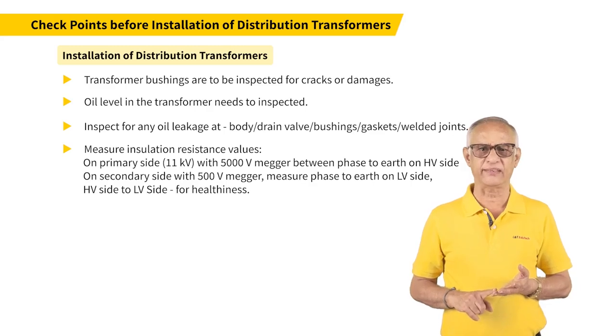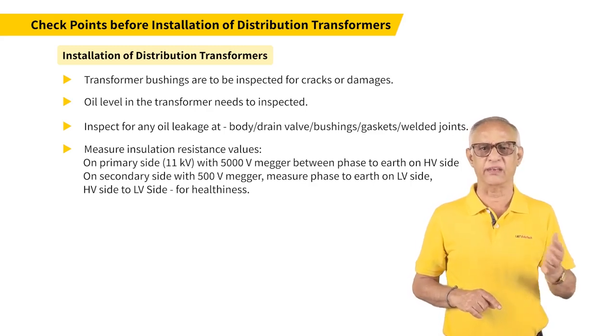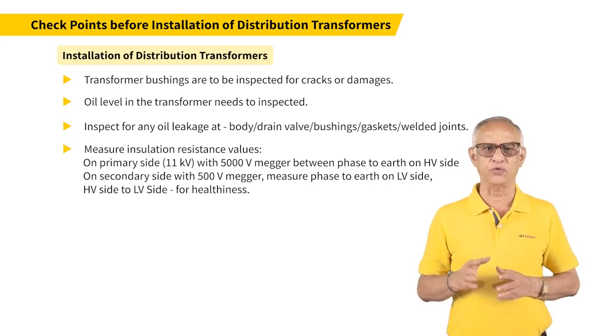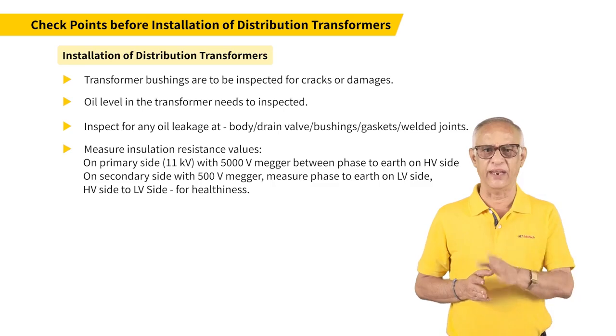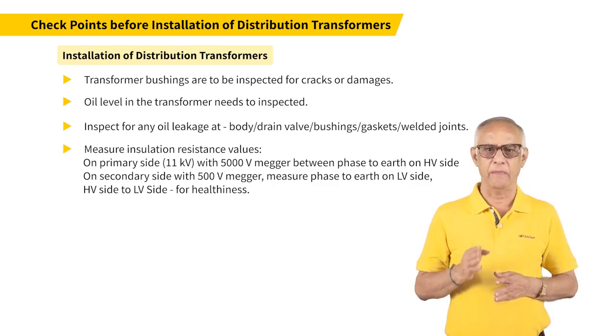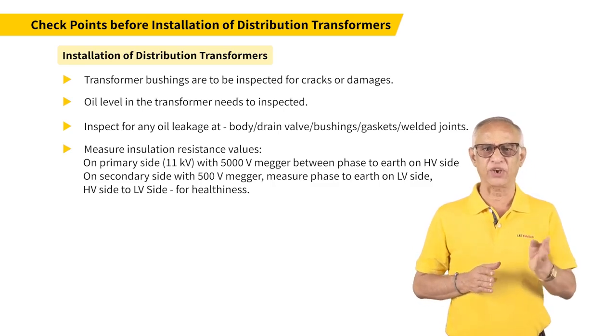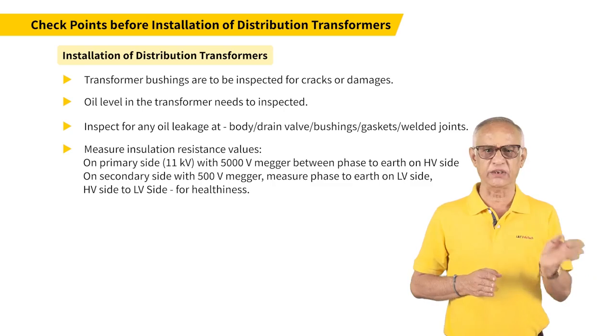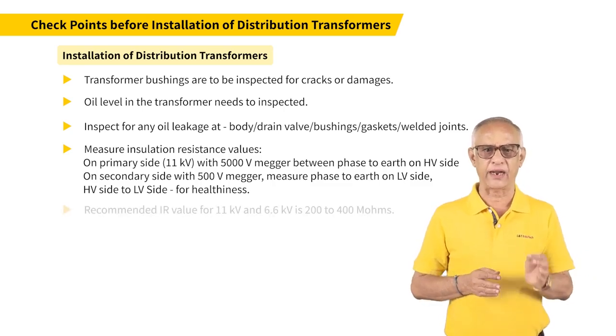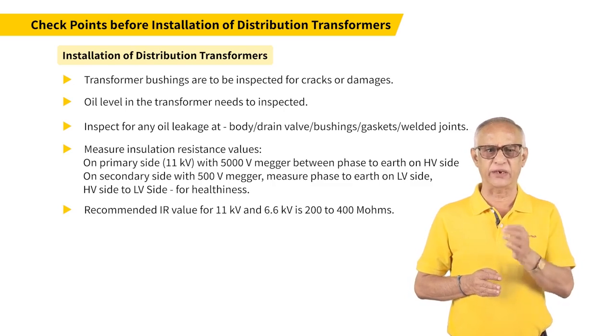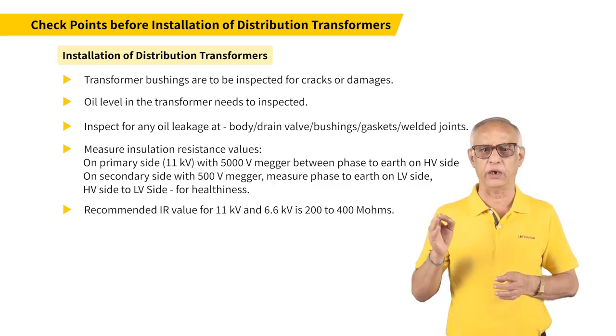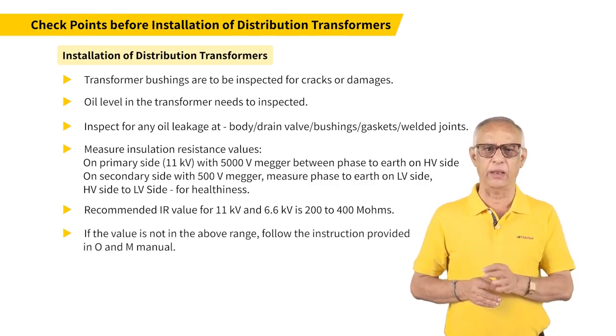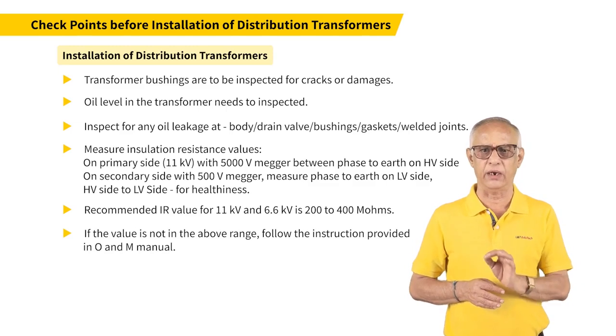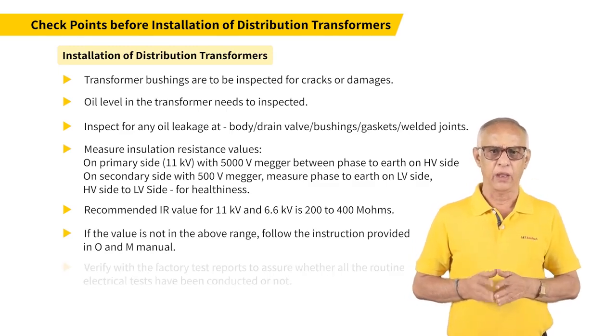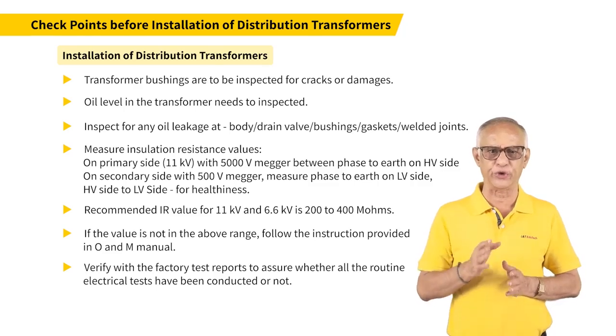Measure insulation resistance values on primary side, that is 11 kV. Measure with 5000 volt megger between phase to earth on HV side. On secondary side, measure with 500 volt megger phase to earth on LV side, and HV side to LV side, for healthiness. Recommended IR value for 11 kV and 6.6 kV side is 200 to 400 megohms. If the value is not in the above range, follow the instructions provided in the operation and maintenance manual. Verify with the factory test reports to assure whether all the routine tests have been conducted or not.